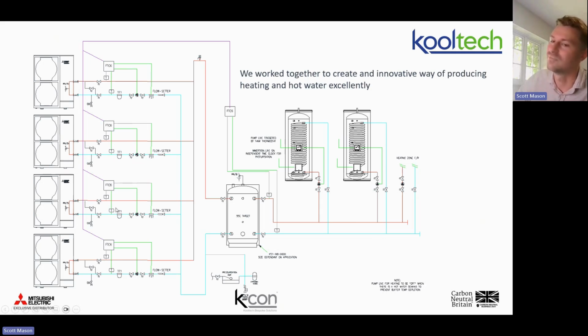So these units don't really know those vessels are there, right? So they can't actually pasteurize it from the heat pump's controller. This is basically the heat pump doing a heating system, and then the heat zone is a coil. So although we're producing hot water, the heat pumps aren't in control of the hot water's destiny. So pasteurization has to be handled external to the actual unit itself. So yeah, we gained a lot of stuff, but we also lost a lot of stuff. So this is the side-by-side thing that I keep referencing. But this is all a part of the dialogue because unfortunately there are so many ways to skin a cat, I guess.